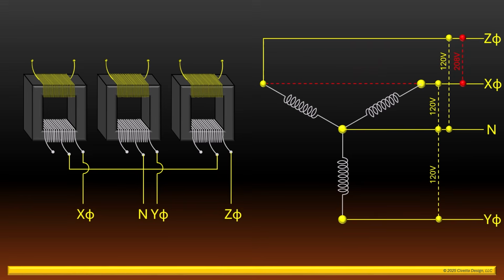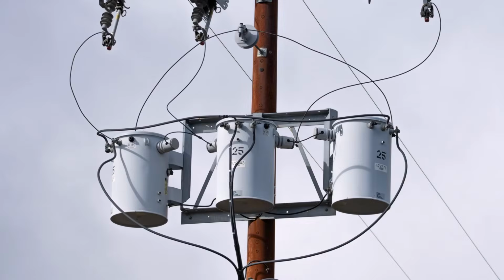The symmetry of this connection also shows us the potential between the Z and Y phases and the Y and X phases is all 208 volts. This is the three-phase power of this Y-connected transformer bank. The secondary Y connection can be seen here. The center tap of each of the three transformers are all connected together with two jumper wires. Along with this lead wire, this all becomes the neutral.